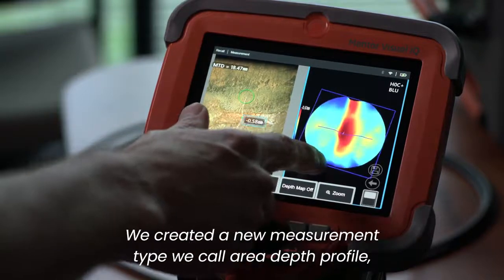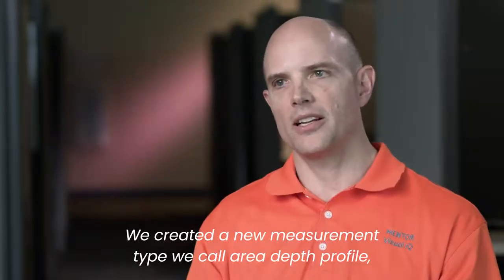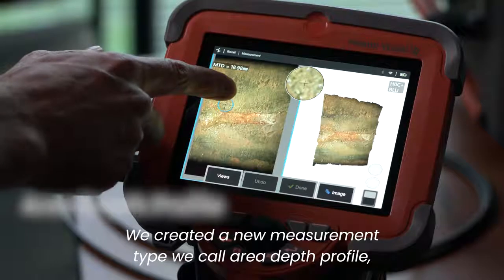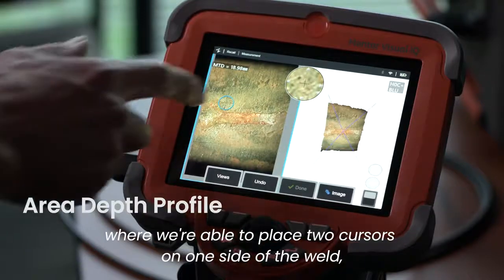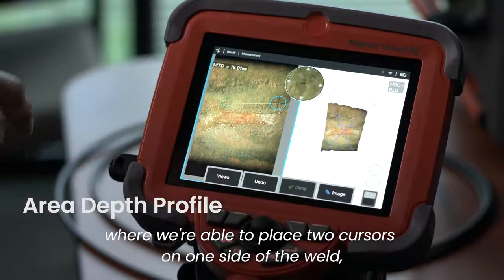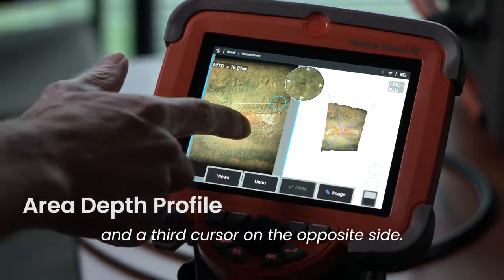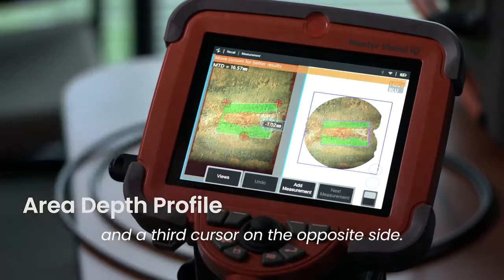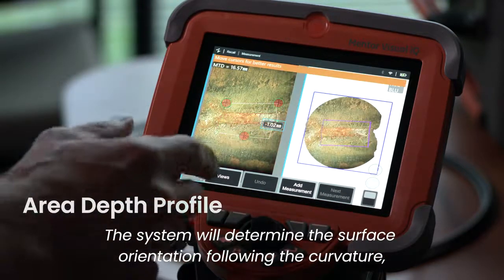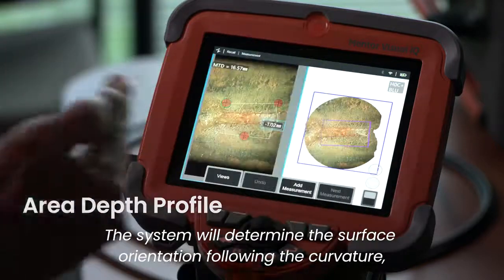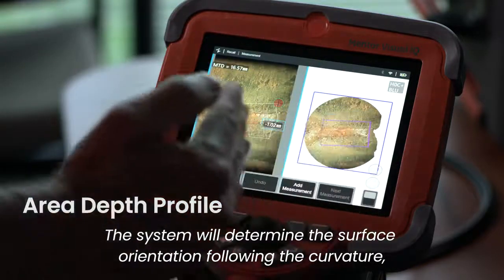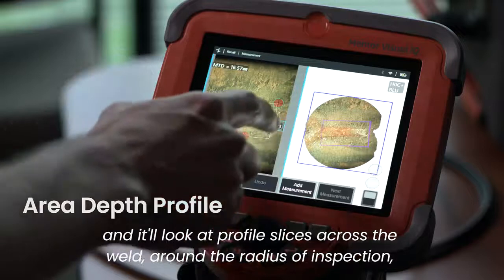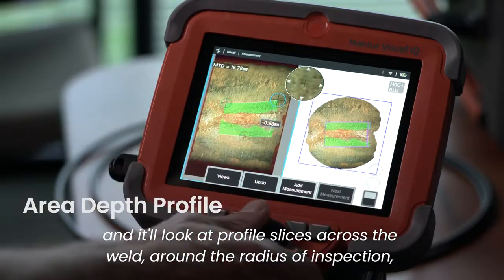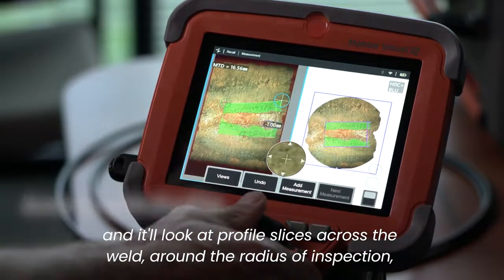And so we created a new measurement type we call area depth profile, where we're able to place two cursors on one side of the weld and a third cursor on the opposite side.